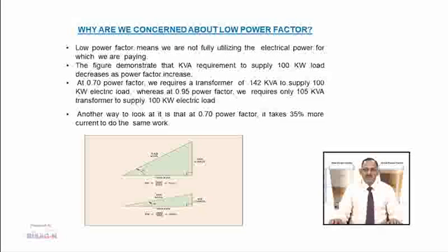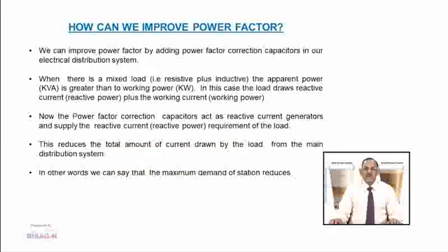As seen in the power triangles, when the actual load was 100 kW and power factor was 0.70, the transformer capacity was 142 kVA and reactive power was 100 kVAR. When the power factor is improved to 0.95, the same transformer supplies the same 100 kW load, but now the apparent power consumed is only 105 kVA and reactive power is 33 kVAR.